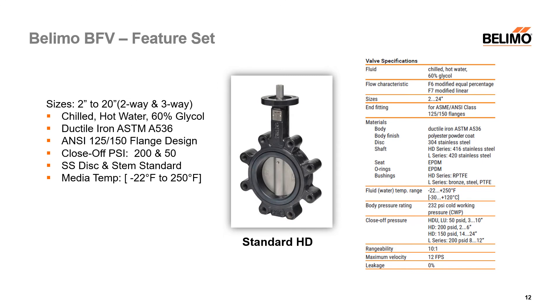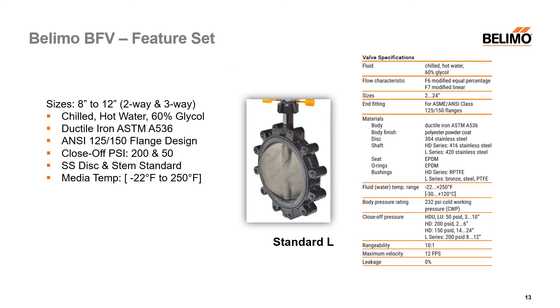Our standard HD and L series come in 2 through 20-inch, both 2-way and 3-way. They are a traditional butterfly valve used for hot and cold water and some glycol, rated up to 250-degree water. Standard disc and shaft are both stainless steel. They are rated at 232 PSI body pressure, with about 200 PSI close-off pressure for the HD and L series. The L series is our newest butterfly that works hand-in-hand with the PR actuator, available from 8 to 12-inch in both 2-way and 3-way.